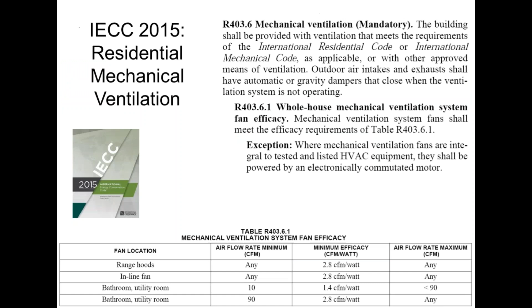The other thing I want to point out, which has nothing to do with Energy Star, is the local code that we follow in Illinois and in many other states. I think we're up to like 14 states that are on the IECC 2015. It's very probable that on most projects you will already need an ECM motor. Because if you're doing a project under the IECC 2015 and you're going to run your ventilation air through the furnace, and by the way, ventilation air is required, if you're going to run it through your furnace duct system and through that blower assembly, then that motor has to be controlled in an ECM fashion. If you have a separate ducting system that brings fresh air in unrelated to your furnace ducting, that's fine. You can do something different. But if you're going to run it through the furnace, it's got to be an ECM. So you're probably already doing that.